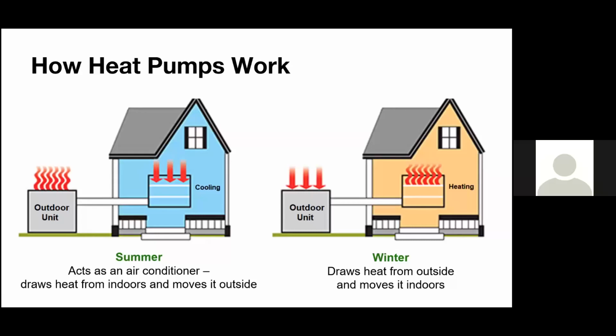The second thing that happens in the winter, on the right, we are essentially air conditioning the outside to heat the inside. And when we air condition something, if you're maybe currently in your house or an office and it's a hot, humid day, and your house or the office is air conditioned, not only would it be at a nice ambient temperature of maybe 70, 72, 75, but it's also dry. That's because in the air conditioning system, in the refrigerant cycle, when you evaporate the refrigerant and cool the air, the air is going to hit its dew point, which is what we call it. So it's going to start wringing out some water, and that's how we dehumidify and keep our buildings comfortable. So that's why all these houses and buildings have these condensate drain pans, condensate pumps, condensate lines that are all grabbing this water that's coming off the coils, that's being wrung out of the air, and then they're putting that somewhere. So in an air source heat pump, the same thing happens in the winter, but outside.